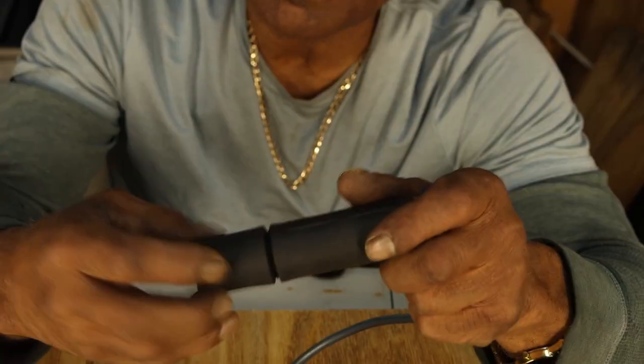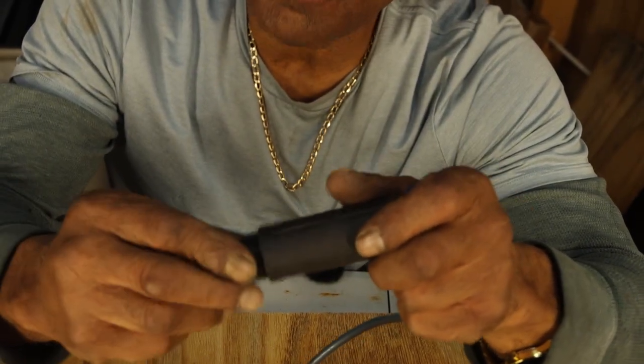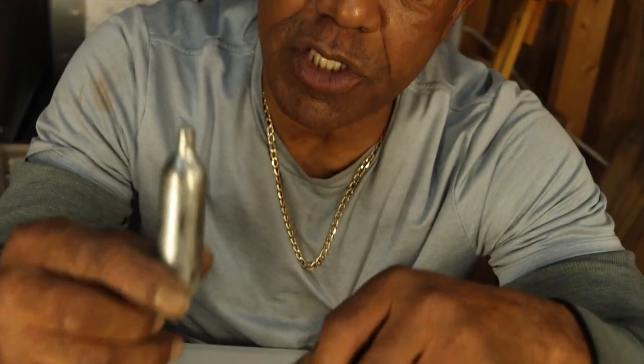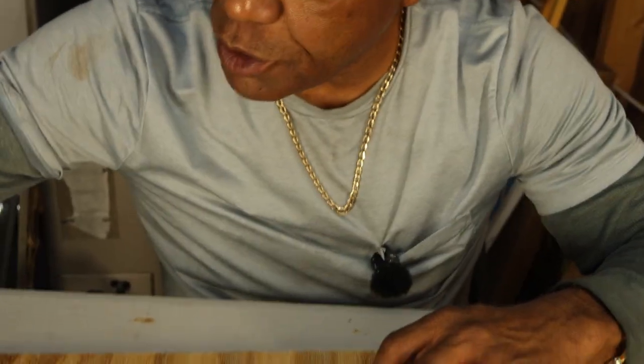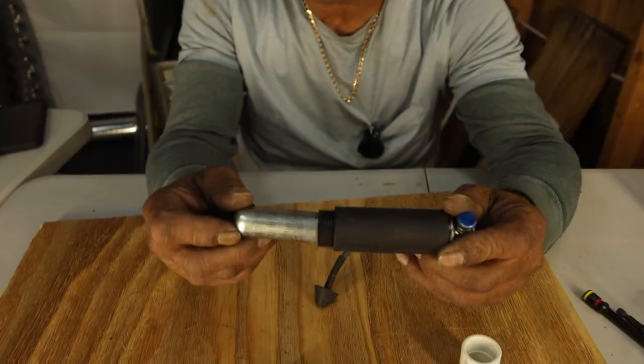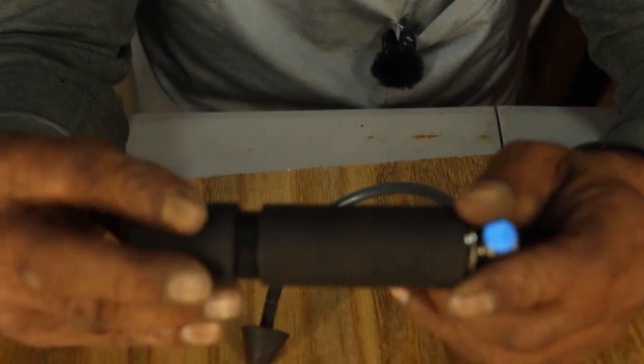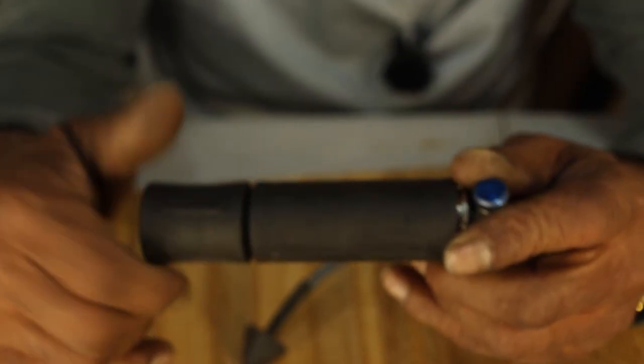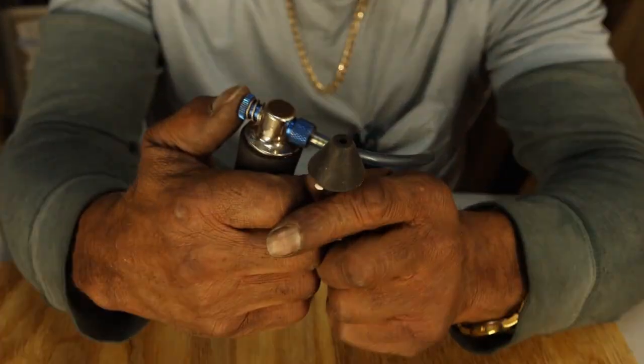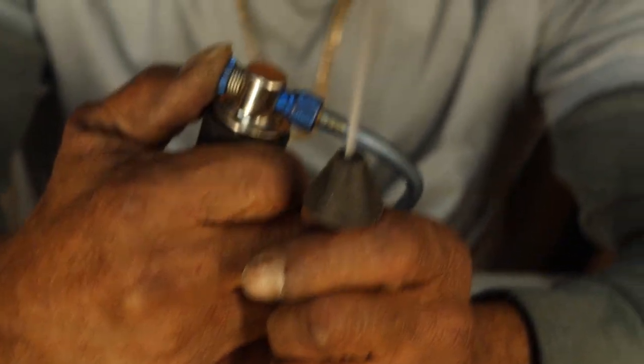The air comes from little nitrogen cartridges that go inside. That one's been used, okay? Just put the cartridge in, tighten it up, and then you're ready to go again. Sometimes you may have to swoosh a line more than once in order to get it clear. But, well, ain't that something? That's quite a bit of air pressure inside a 3/4 inch PVC condensate drain. That typically will blow that line out and clear it and free the drain up.